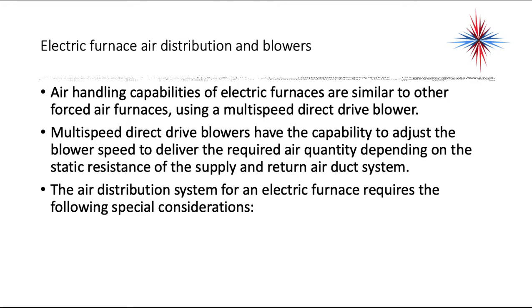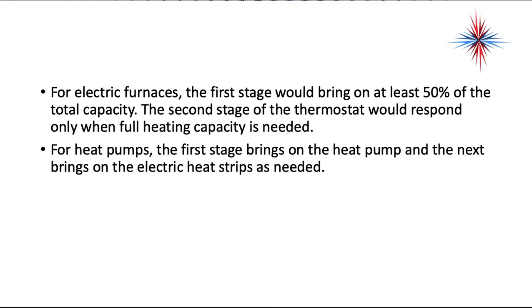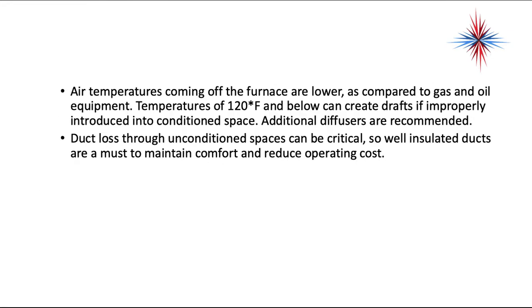Air handling capabilities of electric furnaces are similar to other forced air furnaces using multi-speed direct drive blowers. Multi-speed direct drive blowers have the capacity to adjust the blower speed to deliver the required air quantity depending on the static resistance of the supply and return air duct systems. The air distribution systems for an electric furnace require the following considerations. For electric furnaces, the air temperatures coming off the furnaces are lower as compared to gas and oil equipment.